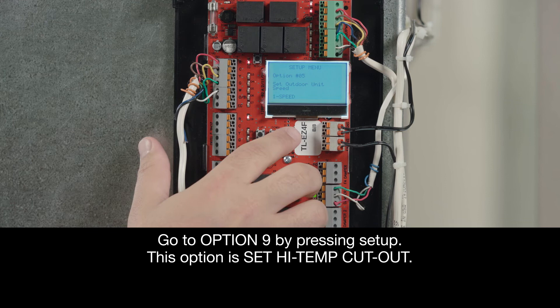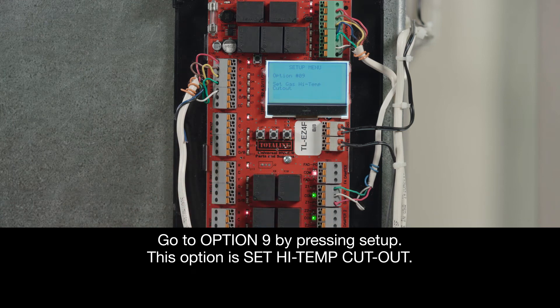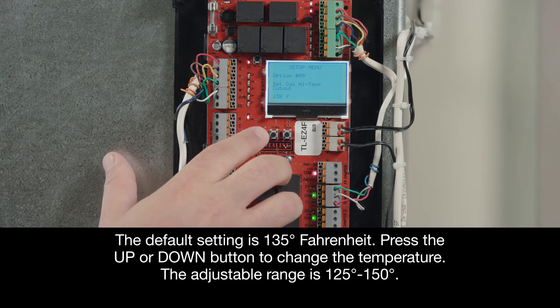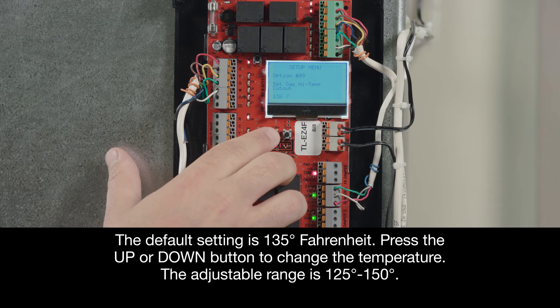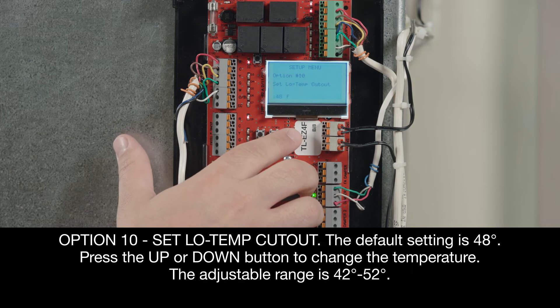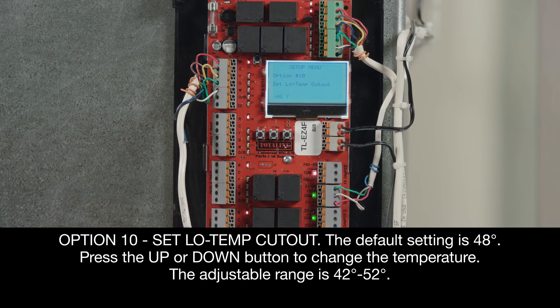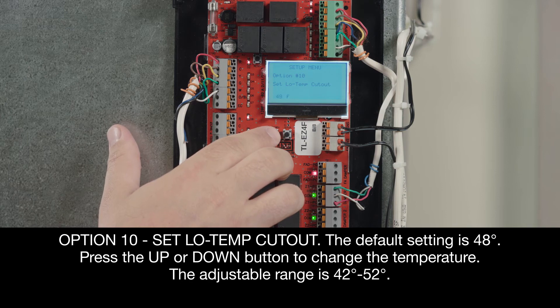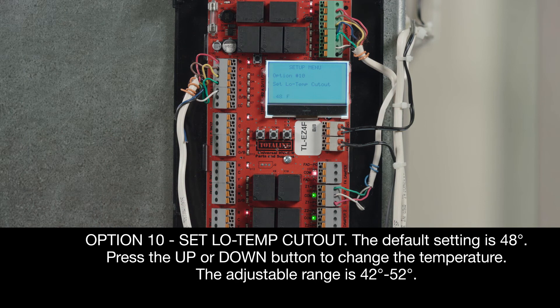Now let's go to Option 9 by pressing Setup. You can see this option is Set High Temp Cutout. The default setting is 135 degrees Fahrenheit. Press the Up or Down button to change the temperature. The adjustable range is 125 to 150 degrees. Next, Option 10, Set Low Temp Cutout. The default setting is 48 degrees. Press the Up or Down button to change the temperature. The adjustable range is 42 to 52 degrees.